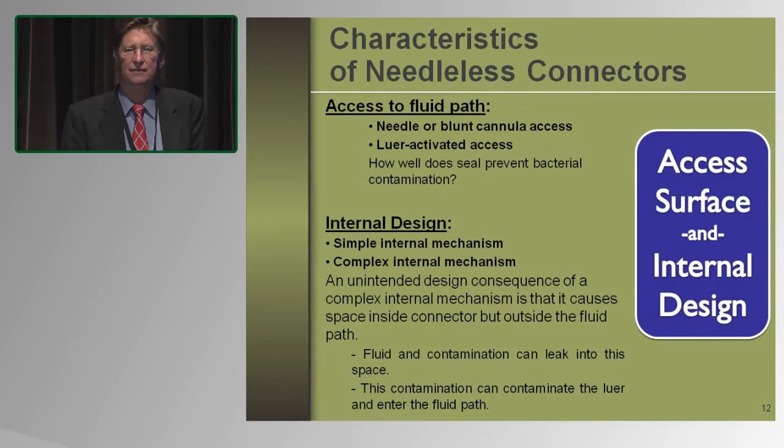So if we look at characteristics of needleless connectors, there's 2 major areas to keep in mind. One is access to the fluid path. Is it done through a needle or a blunt cannula, or is it through luer-activated access? And how well does it seal to prevent bacterial contamination? Second is the internal design. Is it a simple design, or is it complex? And one of the unintended design consequences of complex internal mechanisms, some of which have been developed to produce positive pressure, for example, is that it causes space within the connector, but outside the fluid path. And when the fluid and contamination leak into this space, it then can lead to contamination of the luer and ultimately enter the fluid path.